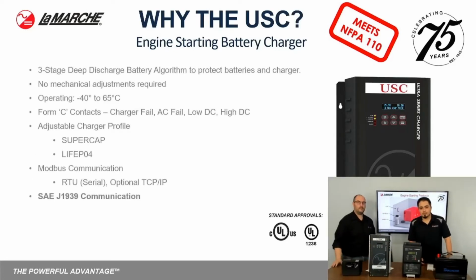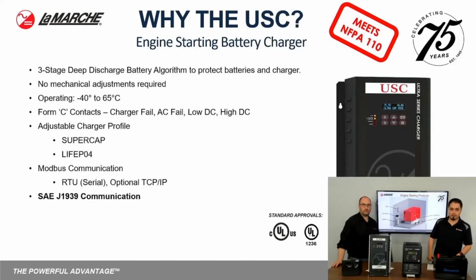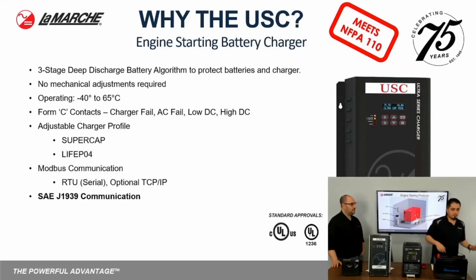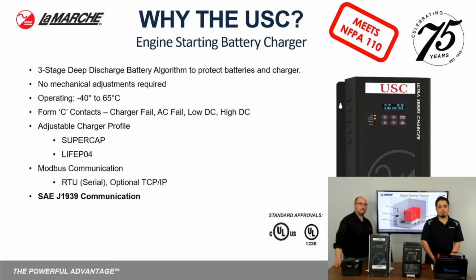So why the USC? The USC has a 3-stage deep discharge battery algorithm to really protect the batteries and the charger itself. There are no mechanical adjustments required on this, so everything you would see is done through the front display, and I'll go through some of the menu adjustments in a moment. It does operate from -40 to 65 Celsius, and there is a derating once you exceed this point all the way up to 70 C as well. It comes standard with Form C contacts: charger failure, AC failure, low DC voltage, and high DC voltage. Adjustable charger profiles, Supercap mode, LiFePO4 mode, and your Modbus communications RTU, and your optional TCP/IP connection.